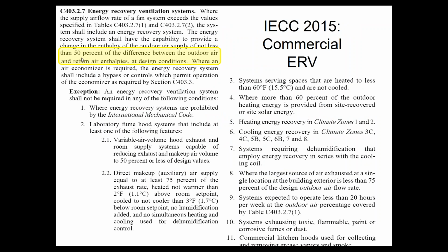The first requirement you have to pay attention to is you have to have 50% enthalpy recovery on your ERV if it's a code required ERV. That means you have to do both sensible and latent recovery. You cannot get 50% of the total if you're only doing the sensible recovery. That means you cannot use heat pipes, you cannot use hydronic wraparound coils, and you cannot use metal fixed plates. You have to use either an enthalpy wheel or an enthalpy core. Those are the 2 ways you'd be able to comply with this.